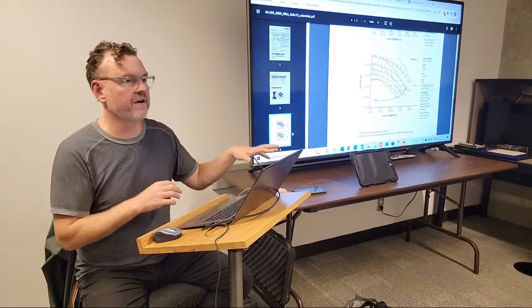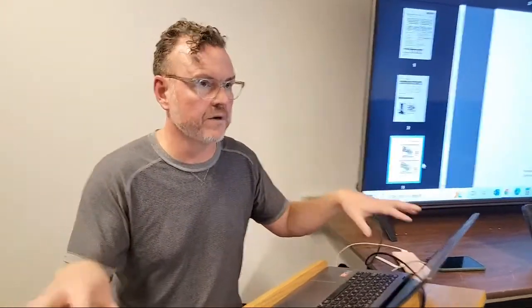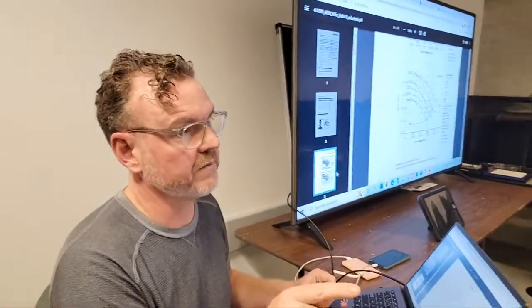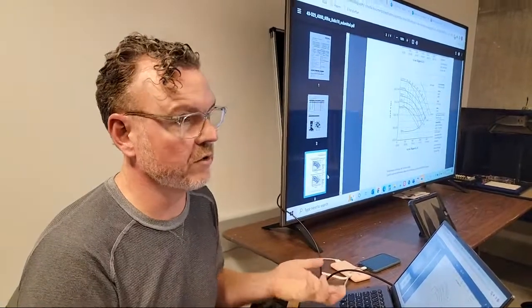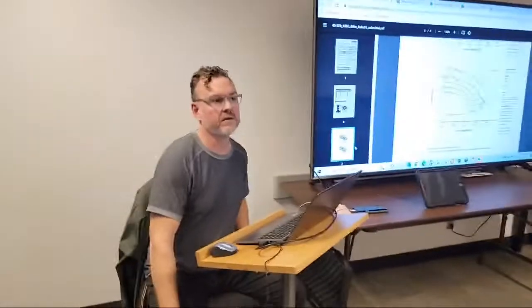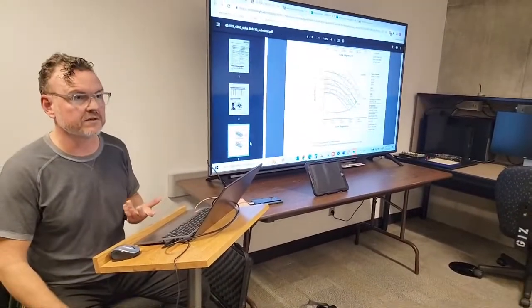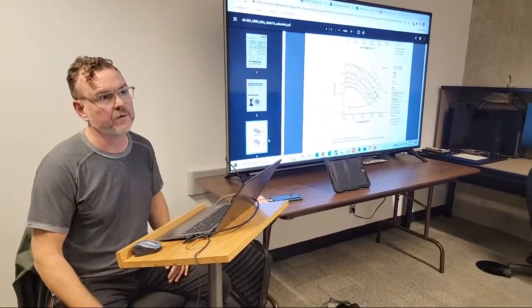So if I have a rooftop unit from one manufacturer and a different air handler from another manufacturer, and they both have supply temperature sensors, if I want to know the supply temperature, I go through the BACnet object list and say that BACnet object equals this supply temp, right? Then the building automation will pull that information and load it into their system. And there are read and write points, and read-only points, right? So there are some objects that you can manipulate, and some that are just data points.